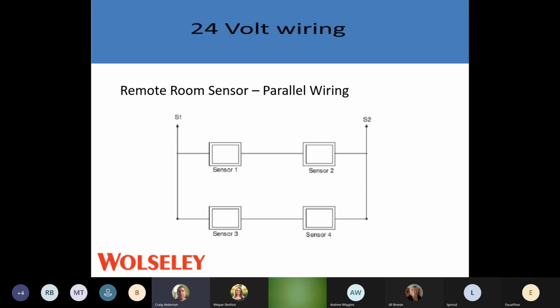Another thing with the communicating system: if you're in a big house and the customer's complaining about air distribution, it's cold over here, it's warm over here. If they have the communicating Ion system, they have the opportunity to add sensors on that system. We can add up to 4 sensors. You could place the 4 sensors around the living area, and it will take the average of those 4 sensors to heat and cool that spot.